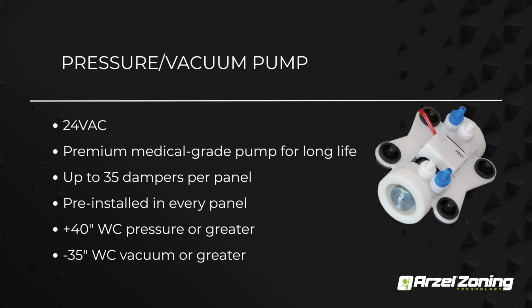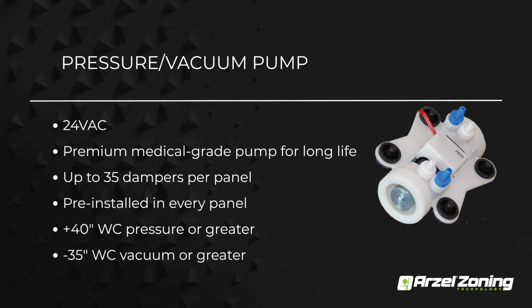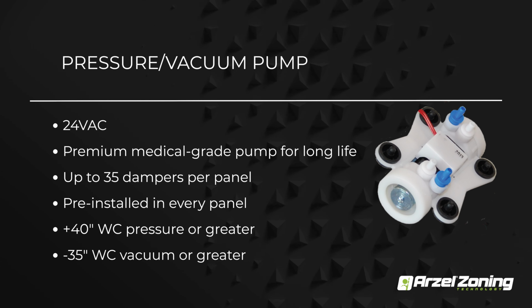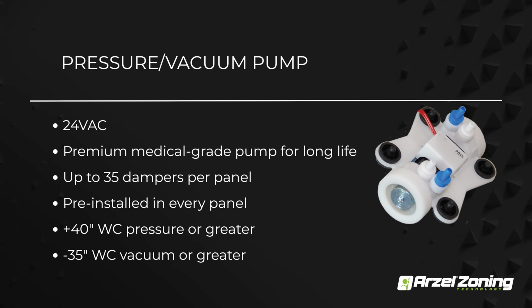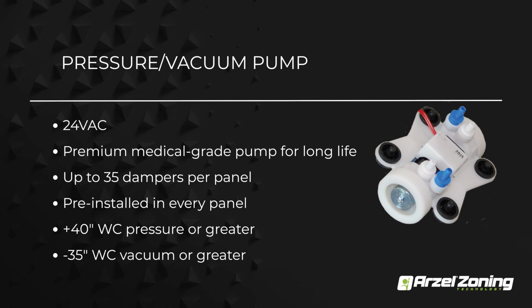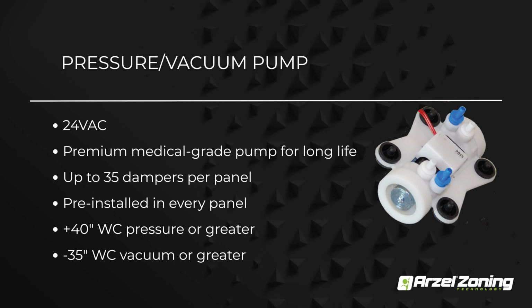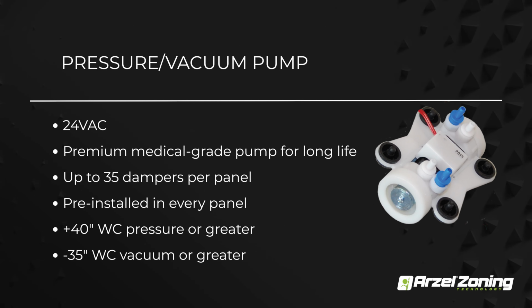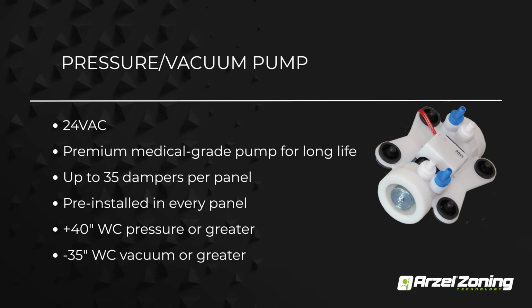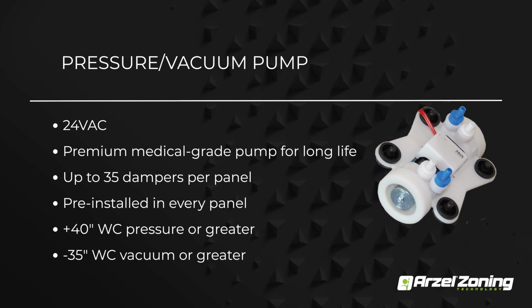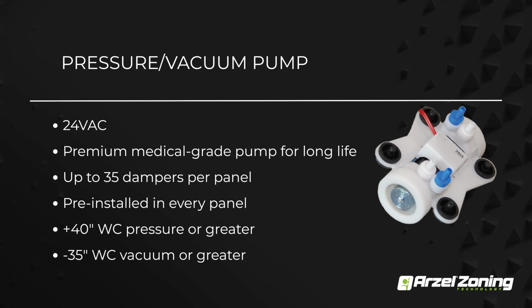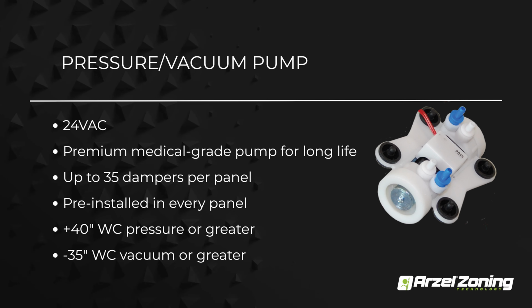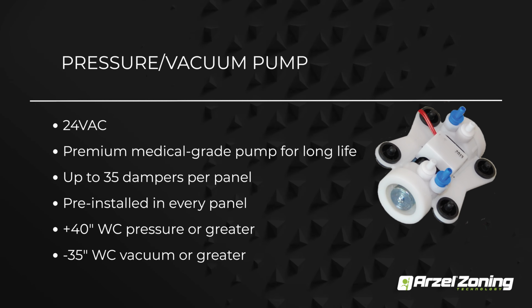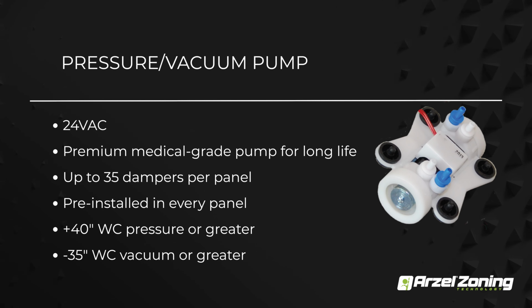Then to make that work, every panel that we offer is going to have the same pump. It was originally designed to be a kidney dialysis pump, so it's a really reliable pump. And this is actually a 24-volt AC pump. It's going to run anytime there's a call on the panel for conditioning, and it's going to supply that vacuum or pressure to your solenoids, which will send that to your damper itself, so either opening or closing those dampers.